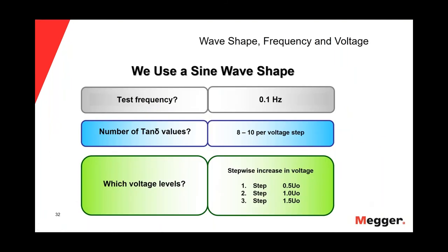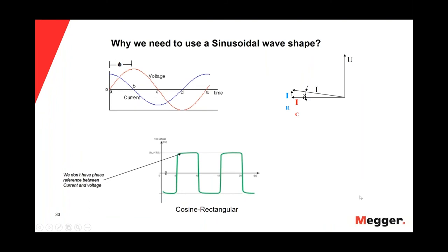To perform the tan delta test, we need to use a sinusoidal wave shape at the frequency of 0.1 Hz. We will measure the tan delta 8 to 10 times per voltage step. The three voltage steps applied are: first 0.5 U0, second 1.0 U0, and third 1.5 U0. Why do we need to use a sine wave shape? Because we use the phase diagram to see the correlation between voltage and current, and we need the phase reference between the peaks of the voltage and the peaks of the current — a reference that we cannot have with a cosine rectangular wave shape.